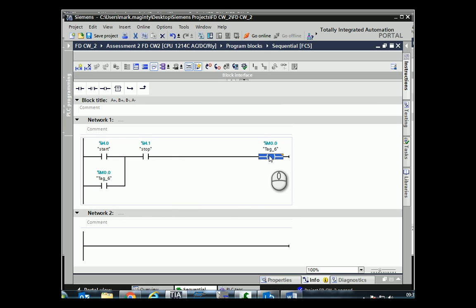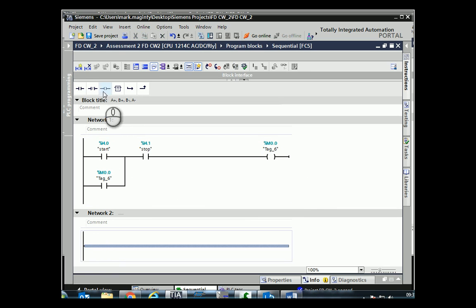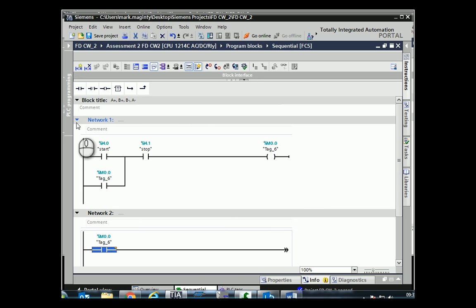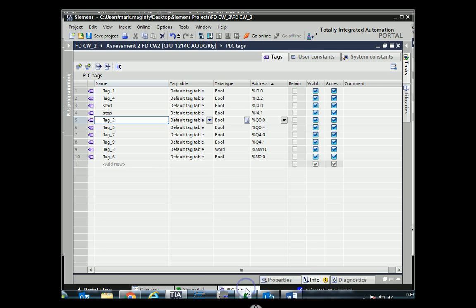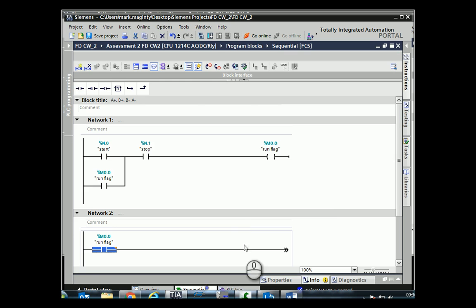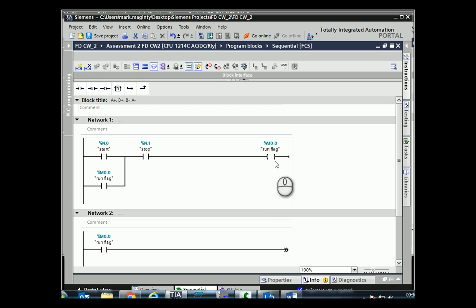We can use M0.0 as a method for the rest of the program to allow it to run or not run. We just need to include M0.0 at the start of every single network. So that's our run flag — anytime the start button has been pressed it latches on the circuit, keeps the run flag on, and stays that way until you press the stop button.